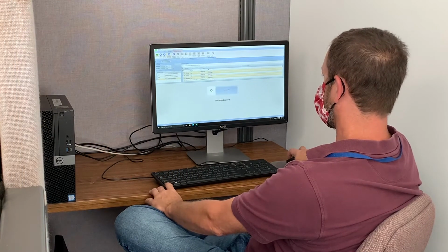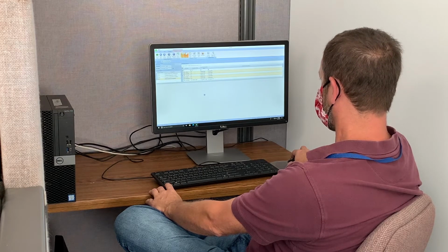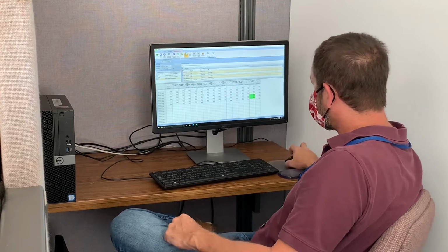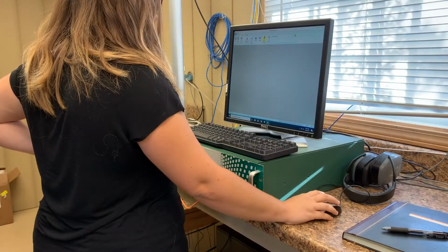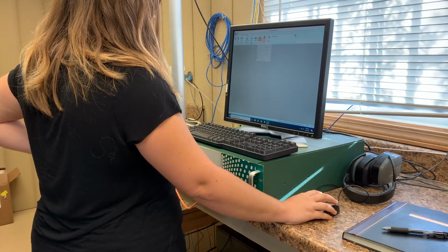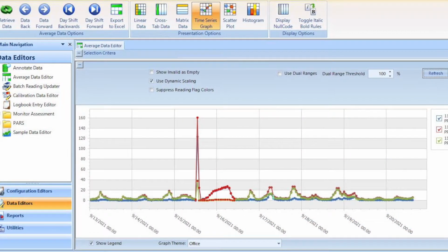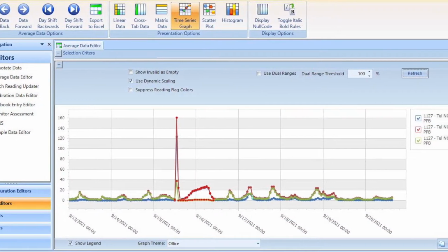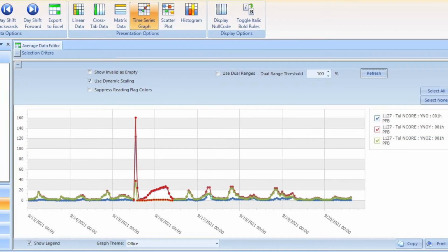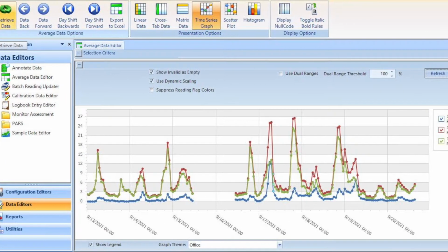The Central Server is located at the DEQ Central Office in Oklahoma City. This server polls each site's data logger every hour and is the permanent storage location for all of Oklahoma DEQ's ambient air monitoring data. At the office, the data is poured over by several people. The instrument operator looks over the data daily to verify the instrument is continuing to work properly. Quality assurance also reviews this data for anomalous readings and checks it with a series of strict data standards. Any data not meeting all standards are flagged or invalidated. Invalid data cannot be used to compare against that pollutant standard.